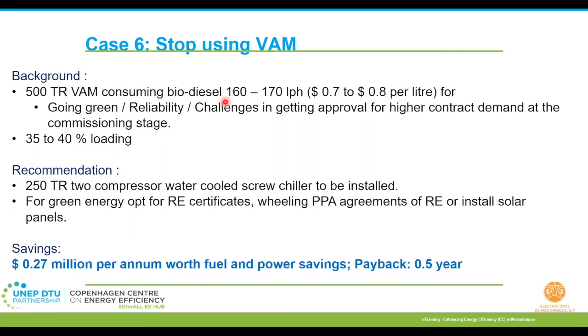For case 6, I will show you why not to use VAM. This was in one of the hospital setups. They had 500 TR VAM machines, which used to consume biodiesel, almost 160 to 170 liters per hour. That's quite a lot of fuel. Of course, they had their reasons when they set up the facility. They had the intention to go green, not to rely on fossil fuel based electrical energy, so they preferred something greener, biodiesel. And they also have a constant, reliable supply of biodiesel, so the supply chain is quite good.